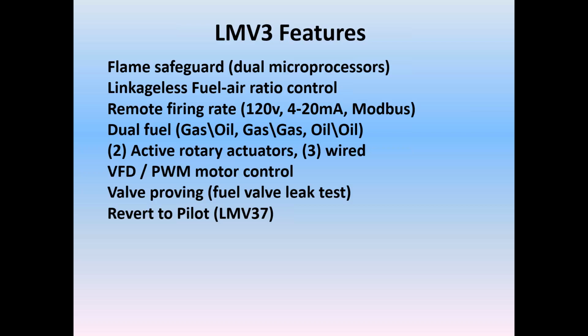shutting the burner down and going into a post-purge, and that becomes inefficient where you cool down the burners, revert to pilot simply relights the pilot and extinguishes the mains, and it stands on the pilot. Then when you get another call for heat, it can immediately relight the mains and you skip the subsequent post-purge, pre-purge, and shutdown sequence. So it makes for a very rapid response boiler, cuts down the cycling time, increases the efficiency quite a bit.